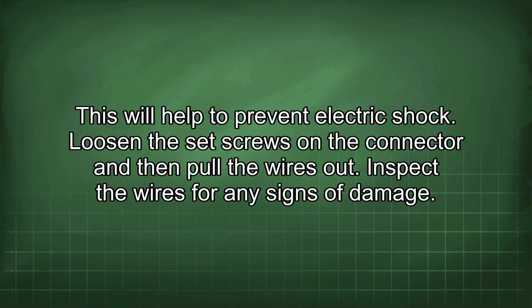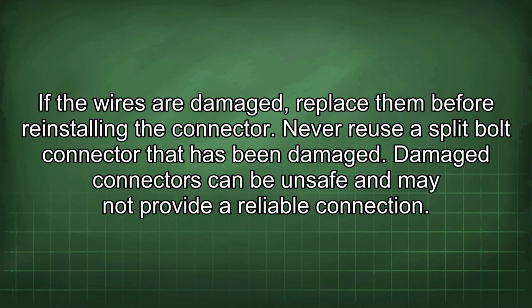Loosen the set screws on the connector and then pull the wires out. Inspect the wires for any signs of damage. If the wires are damaged, replace them before reinstalling the connector. Never reuse a split bolt connector that has been damaged. Damaged connectors can be unsafe and may not provide a reliable connection.